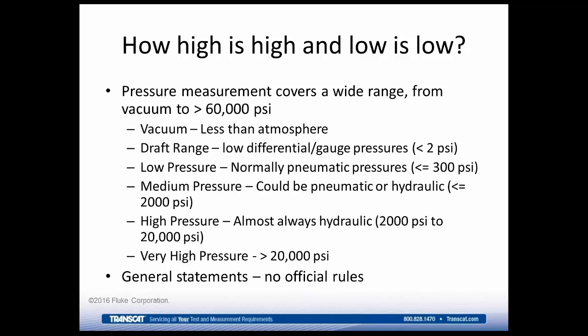The term vacuum is anything less than atmosphere. You can then get into low vacuum, and high vacuum is actually the lowest number of molecules. Draft range is that low differential or gauge mode pressures. So it's the difference in pressure between two rooms, a very, very small amount. Oftentimes it will be measured here in the US in a unit like inches of water, or internationally using Pascal or millibar.